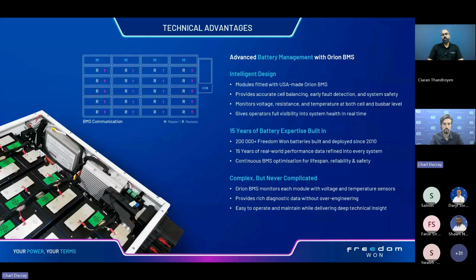So each master monitors the voltages and currents. It monitors for over voltage protection and under voltage protection. It controls the contactors for safety of that tower itself. And between the masters, there's also a CAN communication line, so that one master assigns itself as the main module to communicate back to the EMS or to the inverter. Once that's assigned, it communicates back all the string values to your centralized EMS.